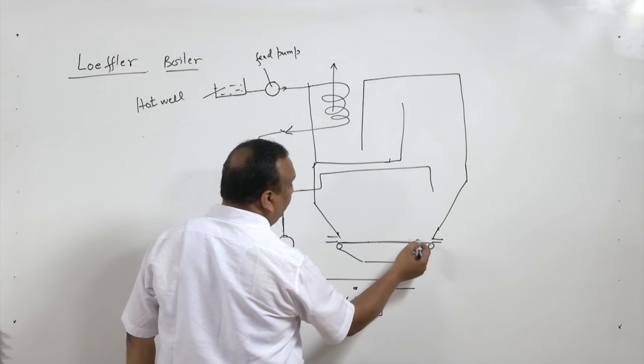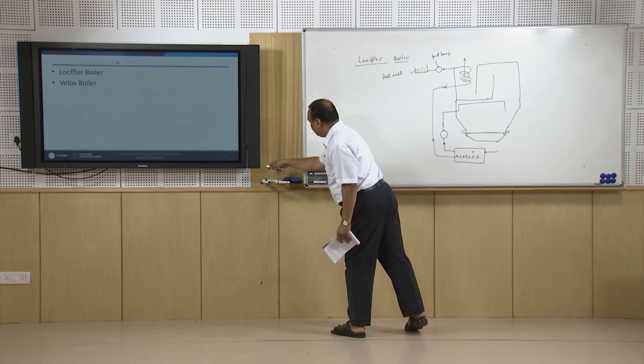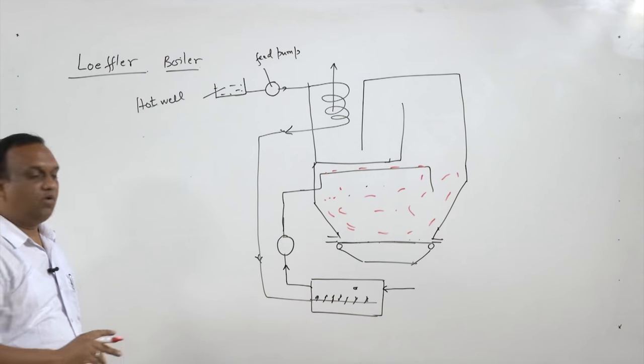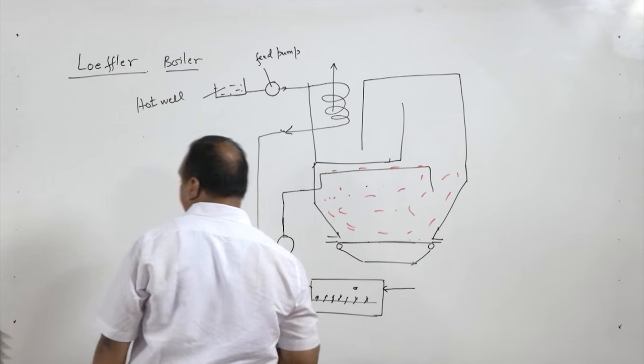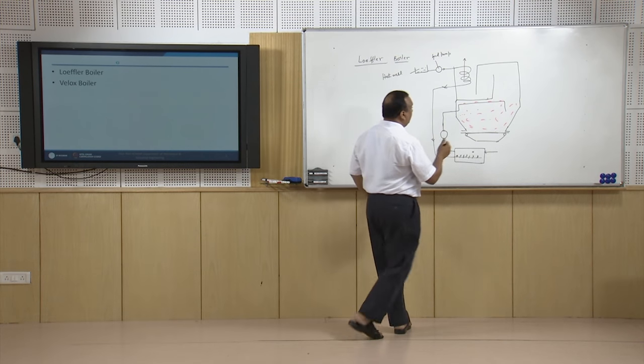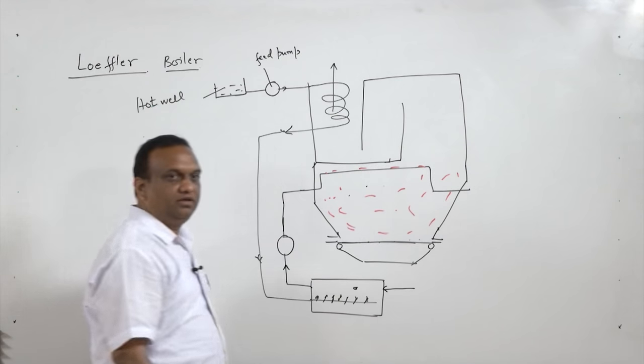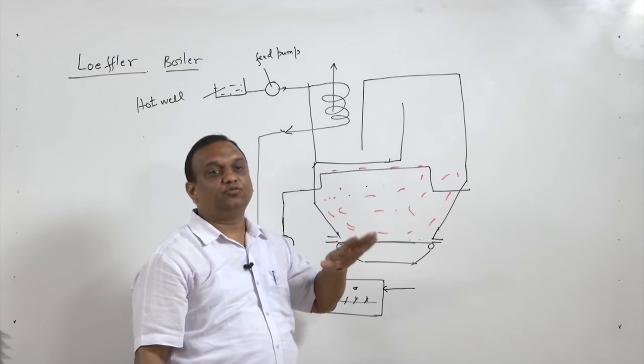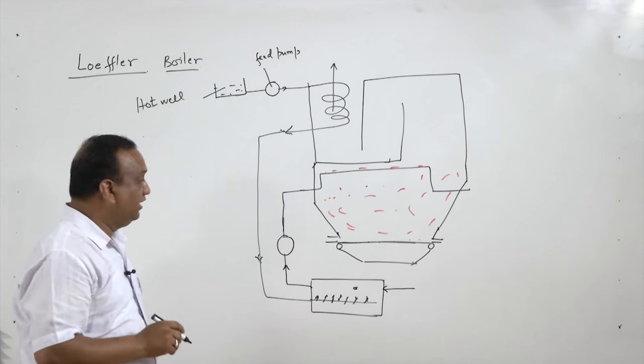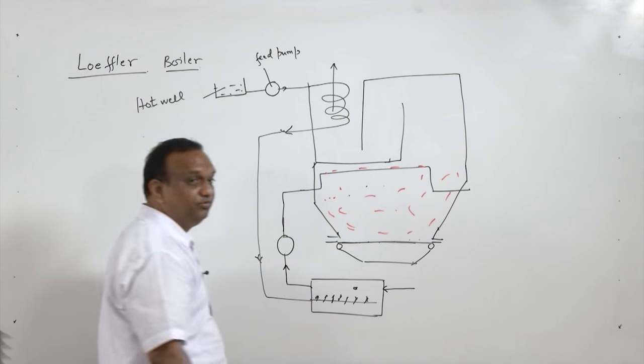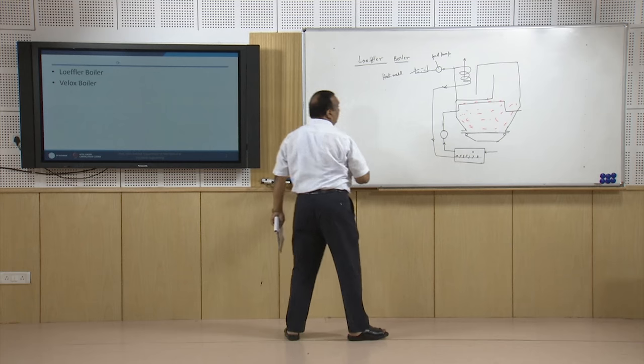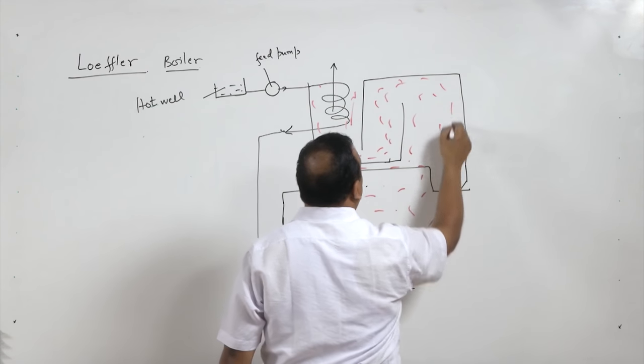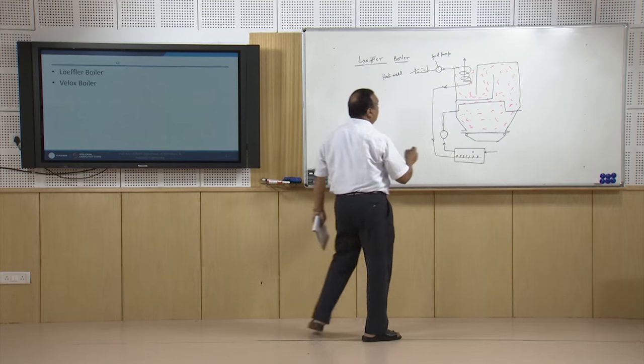The shell is filled with flue gases because burning of fuel is taking place, so the entire space is filled with flue gases. The water circulated in these tubes is heated and subsequently converted into steam. We can directly get saturated steam from here, but as standard practice we have to superheat the steam, especially because this superheated steam will be used for converting water into steam in the evaporation drum. This area is also filled with flue gases, separated by walls.